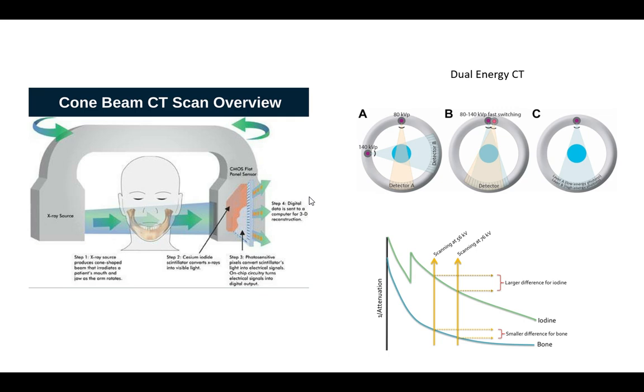So this is done a lot for head, dental, things like that. It's a one-shot deal, so it's even crazy faster. And essentially, you can do the same type of process. You're just using the entire amount generated from that source, so it's a little more efficient on your source as well. Instead of having a fan beam, you're capturing the subsequent layers by the cone shape. Make sense?